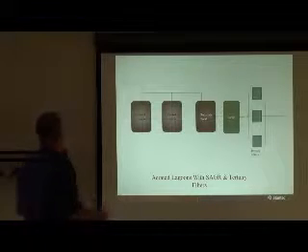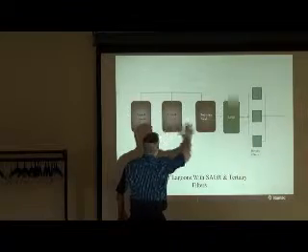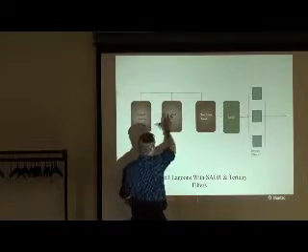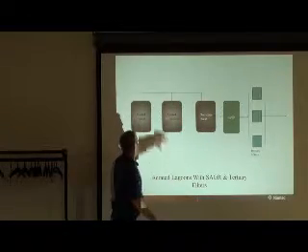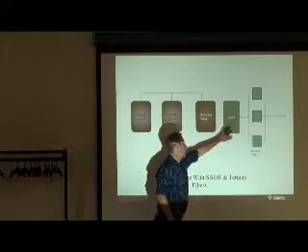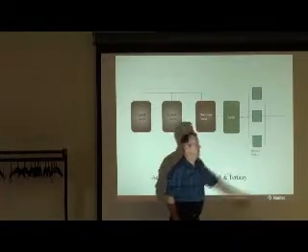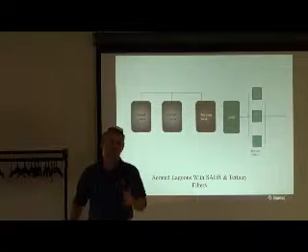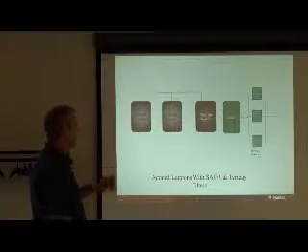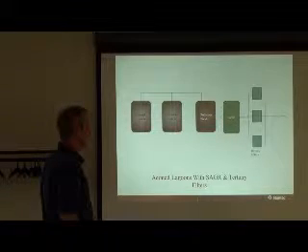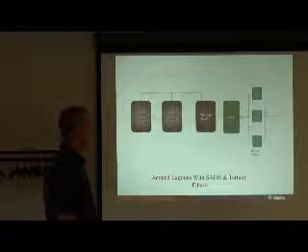So you do the standard stuff, the BOD and suspended solids that your current lagoons are doing now. You do it better because you've added aeration, and then you settle out all that stuff that you've treated. Then you deal with your ammonia through the SAGR process, and you deal with your phosphorus through the tertiary filter. So that option definitely can use the existing footprint. Will that treat the full build-out requirement, 4,600? We believe so, yes.